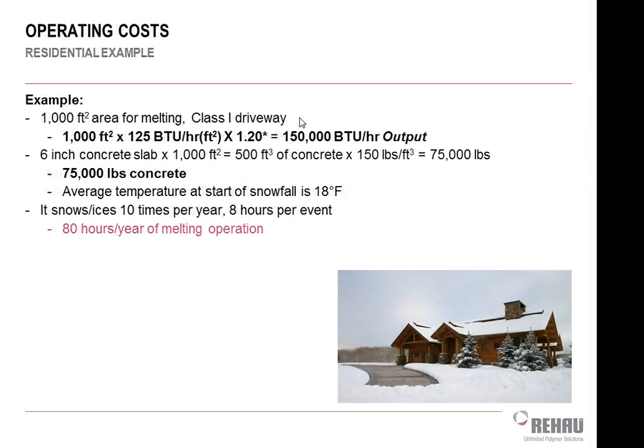All right, so here's some examples here. Here's a residential system. This one is for 1,000 square foot of melting, class 1 driveway, which means we're sizing it to handle pretty much 97-98% of the snowfall hours of the year. If you looked at Bill's cheat sheets, we needed about 125 BTUs per hour per square foot. So that's where that number is coming from here. So this is basically boiling down to needing 150,000 BTUs of boiler output, which means I'm going to be buying a 160 or 180 degree input boiler.